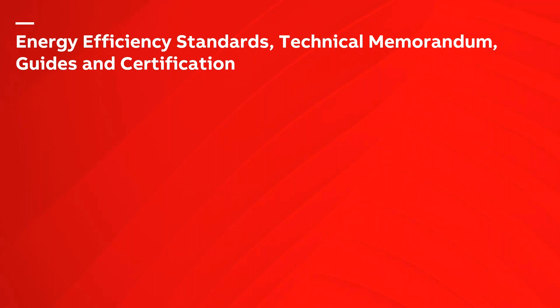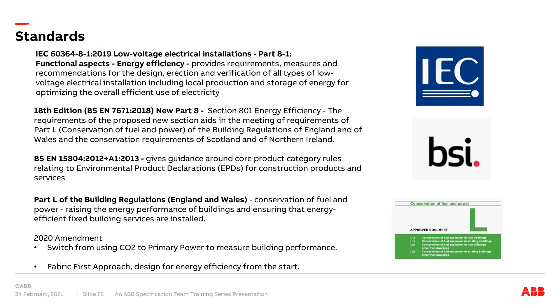So what's going to make this happen? Energy standards, technical memoranda, guides and certification. The IEC 60364-8-1:2019 standard — Low Voltage Electrical Installations, Part 8.1, Functional Aspects of Energy Efficiency — stipulates requirements, measures and recommendations for the design, erection and verification of all types of low voltage electrical installations, including local production, storage of energy, optimisation and overall efficient use of electricity. In the UK we've adopted the IEC standard and incorporated it into BS 7671, the 18th edition. There is a new Part 8, not yet published, which will follow through from an energy efficiency point of view and will probably mirror IEC 60364.